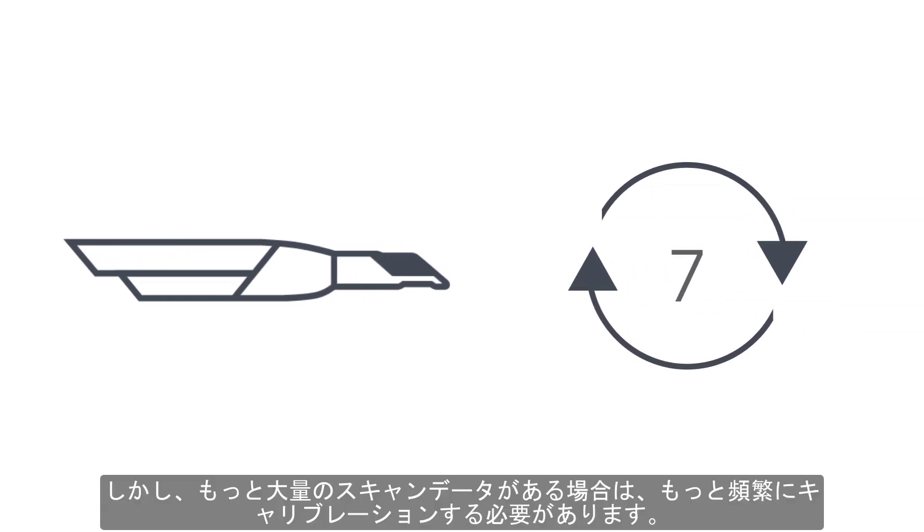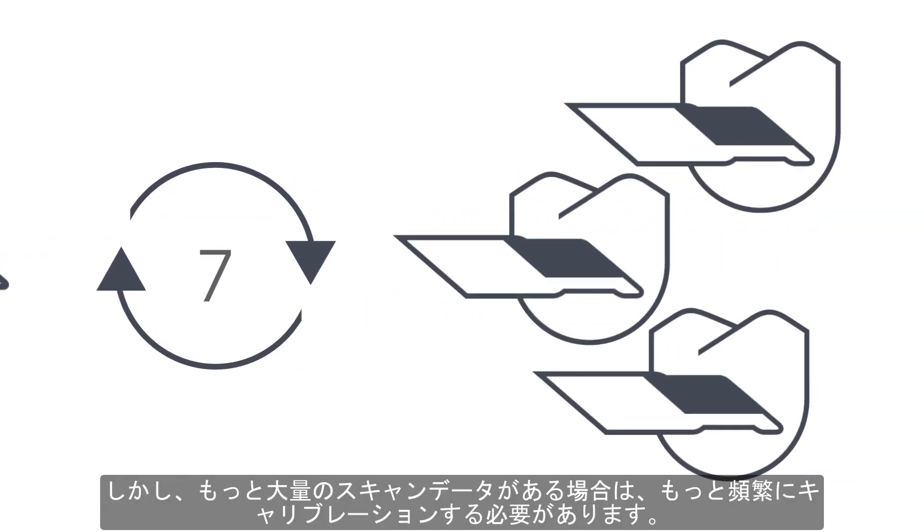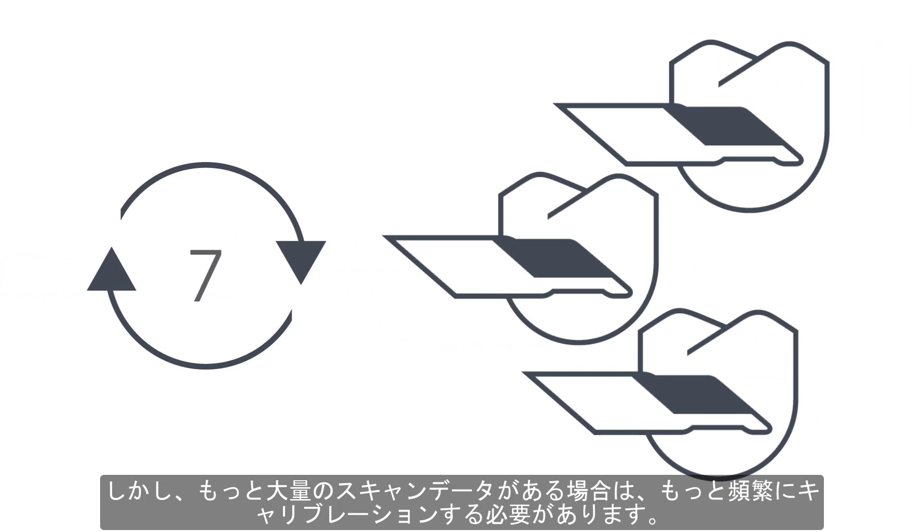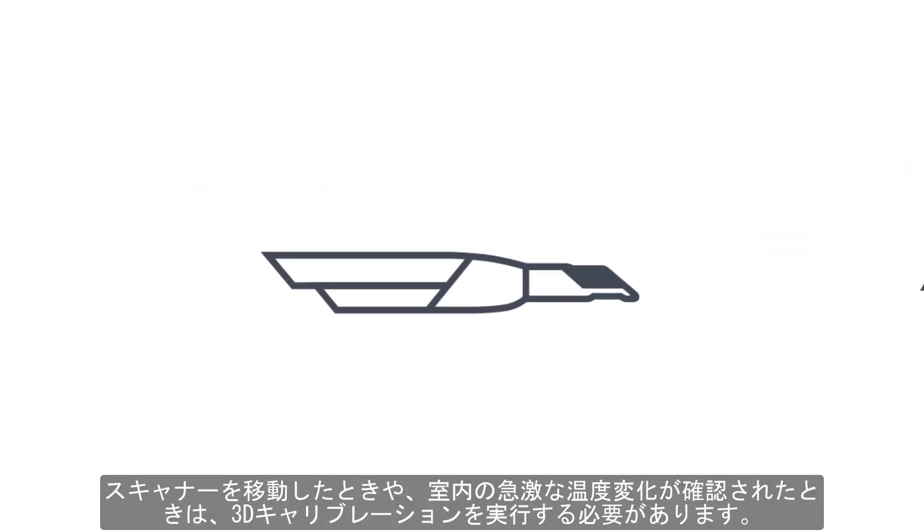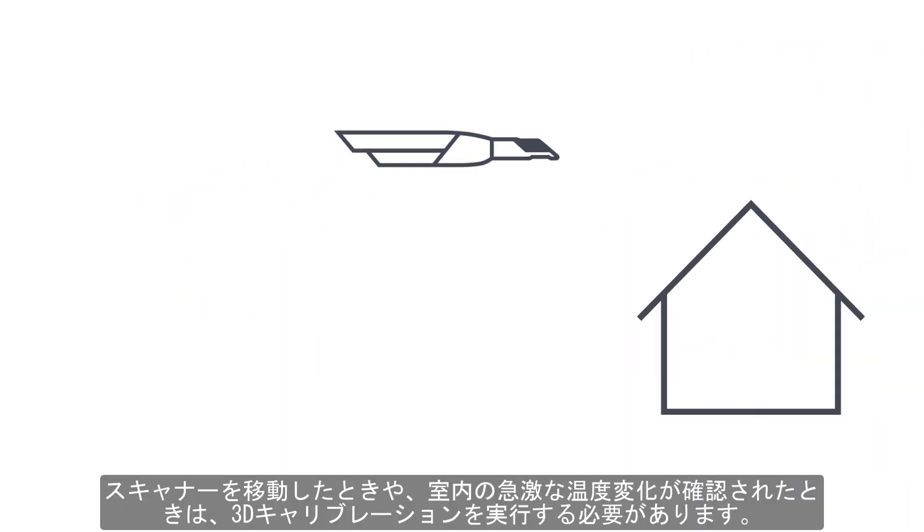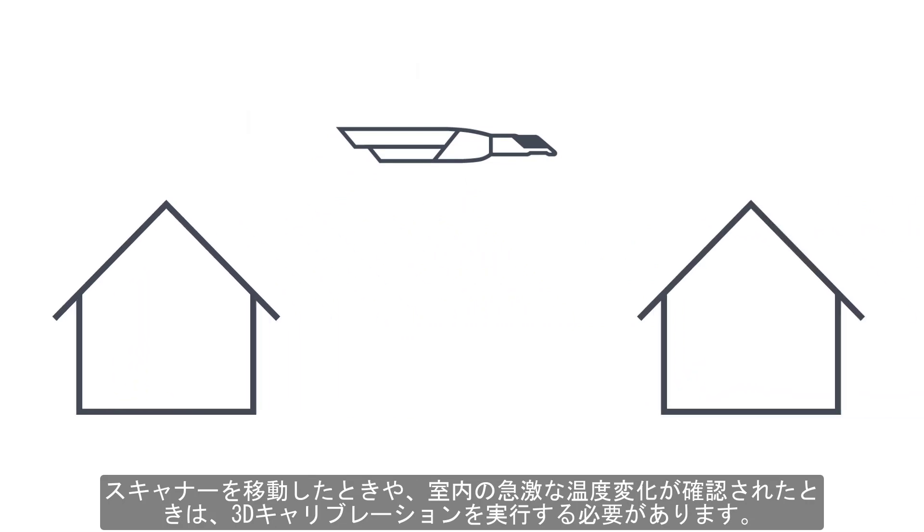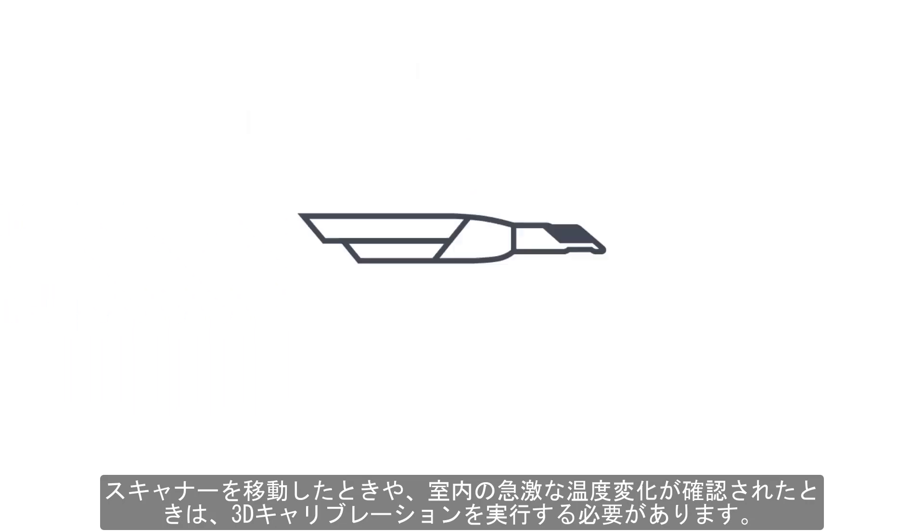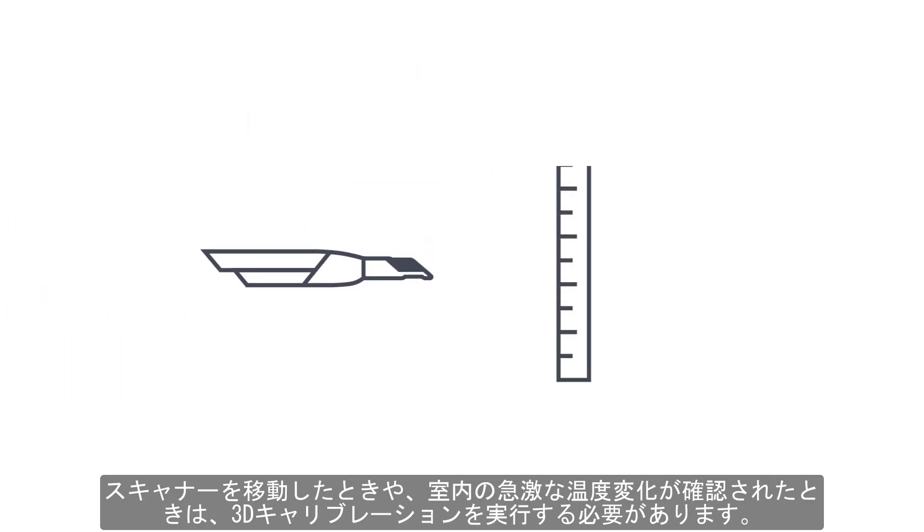However, if you have a more extensive amount of scans, you should calibrate it more often. The scanner should always be calibrated after it has been moved, shaken, or sustained wide-range temperature changes.